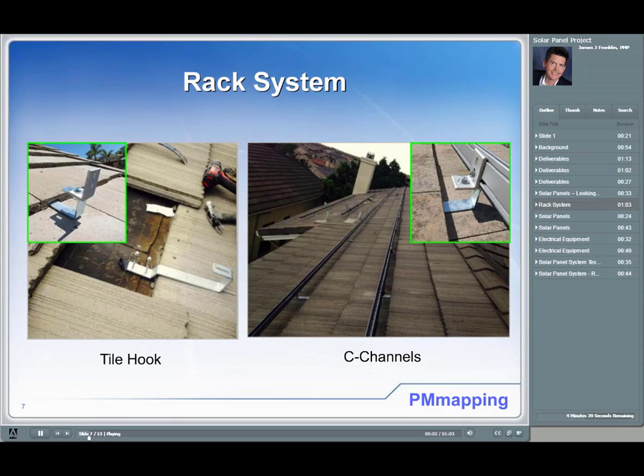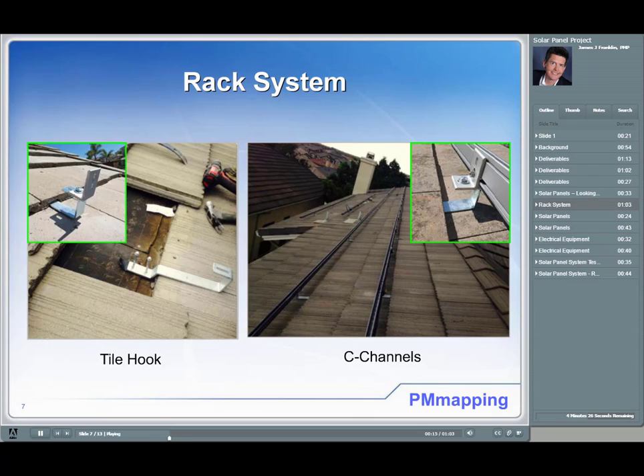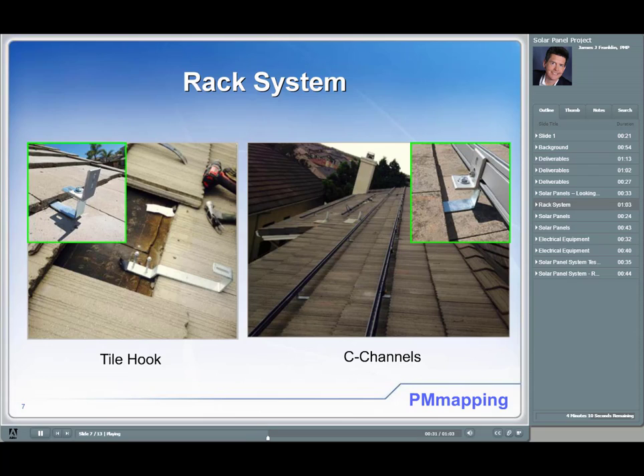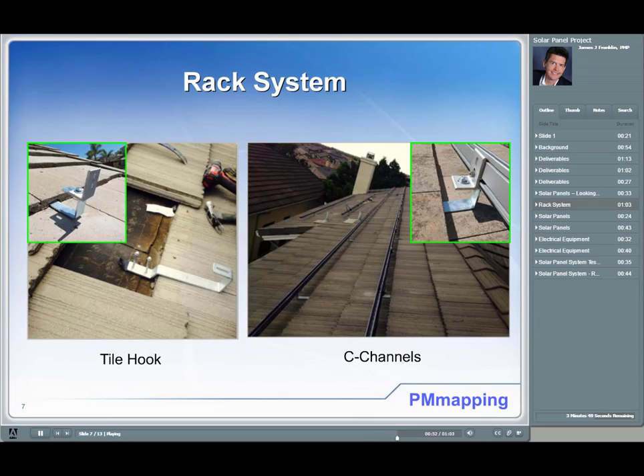These photographs show the rack system — the system on which the solar panels are installed. You can see there's a tile hook, a prefabricated piece of steel drilled into the roof, with sealant material to prevent water entry. From the tile hook, an L-type clip is attached, where the C channels are then installed. Looking to the right of the photograph, you can see the C channels running along the top of the roof — this is where the solar panels get bolted on. It's Stellar Solar's system and I was very impressed, ensuring panels are secure and there would be no leaks, even in an El Niño storm event.